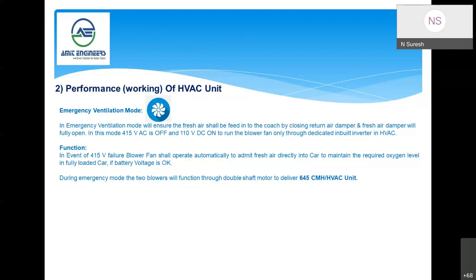There is an emergency inverter built inside the system, which is supplied by MEDHA Servo. The input power is taken from the battery, 110 volt DC, and the inverter will convert it and give an output of 415 volt, and run the blower fan, that is, the double shaft blower motor will run and the fan will start working. In this case, the return air damper will close and fresh air will keep feeding inside the coach, so that the passengers will not feel any discomfort. The amount of fresh air fed per HVAC unit is approximately 645 cubic meters per hour.